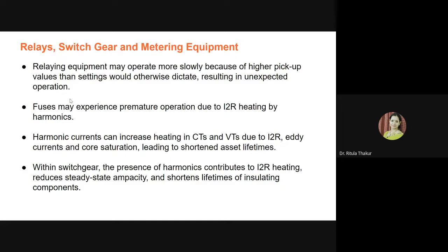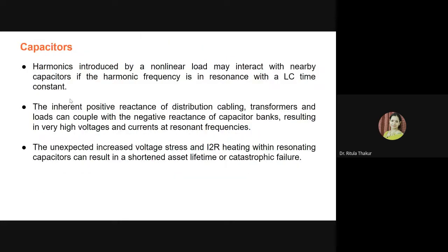And if we talk about the switchgear, again the presence of harmonics contributes to I-square-R heating, which reduces the steady state ampacity and shortens the lifetime of mainly the insulating components. Now, if we talk about the capacitors, the harmonics caused by the charging stations of the e-buses may interact with the nearby capacitors. So there is a term called resonance.